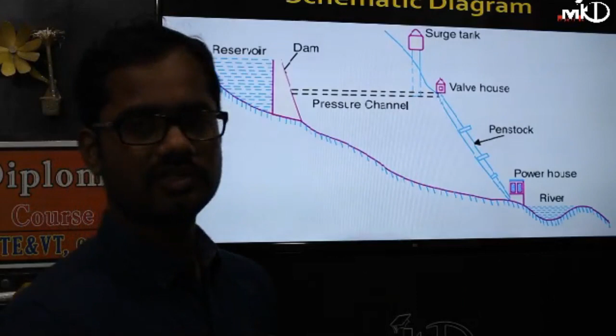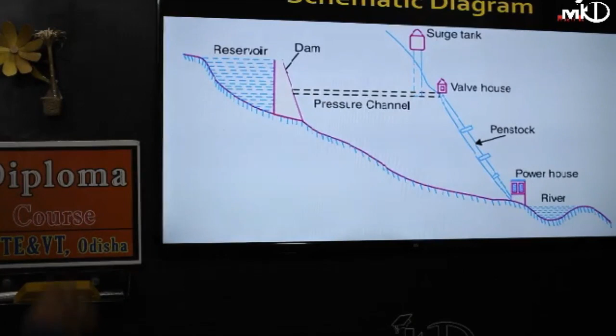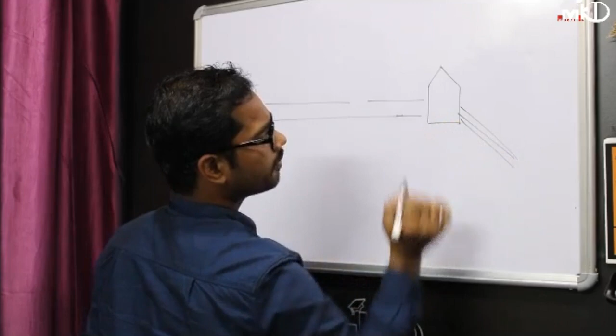So look at the board. I will explain what the function of the surge tank is, how it removes the surges. Look here. The surge tank is simply a tank or an open well, and its bottom is connected with your pressure channel. Take that case. This is your reservoir where water is present. The pipes are there like that, and this is your valve house, and these are the penstock. So the surge tank is present like here.